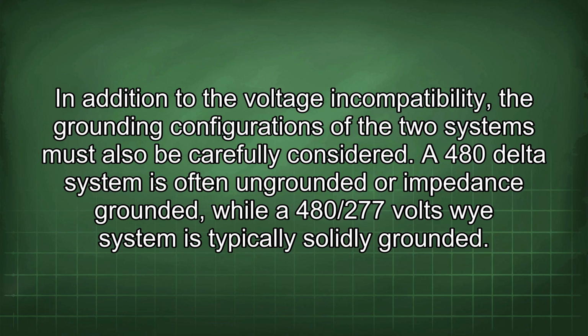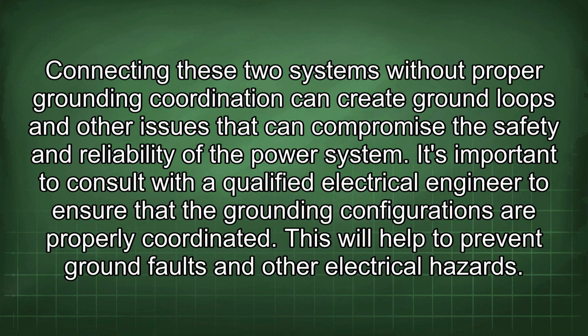A 480 delta system is often ungrounded or impedance grounded, while a 480/277 volts Y system is typically solidly grounded. Connecting these two systems without proper grounding coordination can create ground loops and other issues that can compromise the safety and reliability of the power system. It's important to consult with a qualified electrical engineer to ensure that the grounding configurations are properly coordinated. This will help to prevent ground faults and other electrical hazards.